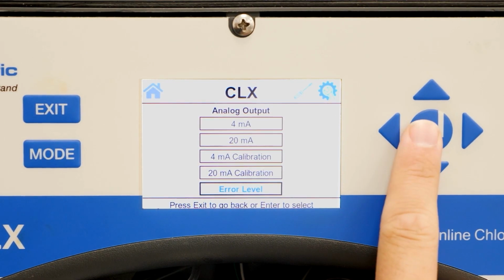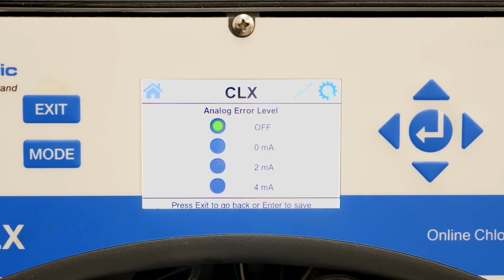The error level option allows you to have the CLX send a certain milliamp signal when the analyzer has an error. Using the 0 or 2 milliamp options will allow the SCADA system to display a negative number or an out-of-range value when the analyzer is in a warning or error state.